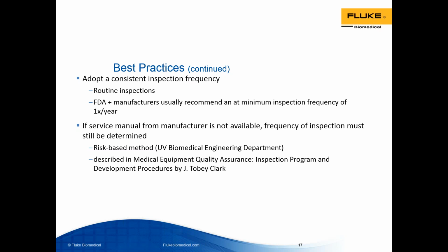As we've talked about throughout most of this webinar, an infant's first few days of life can be their most critical, which is why it's important to routinely test and verify the safety and performance of infant incubators and adopt a consistent inspection frequency. So check the manufacturer's service manual for the frequency recommendations. The FDA, along with most manufacturers, will recommend a minimum inspection frequency of once per year.